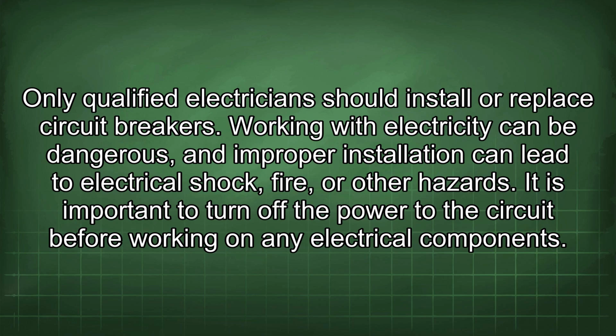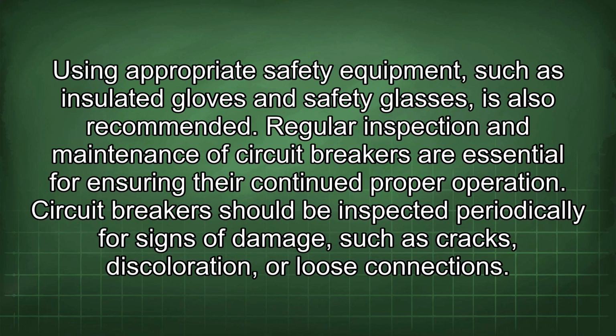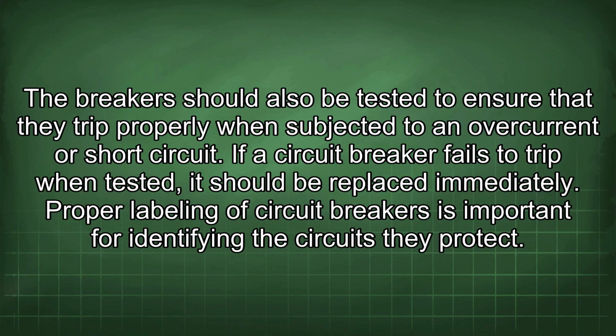It is important to turn off the power to the circuit before working on any electrical components. Using appropriate safety equipment, such as insulated gloves and safety glasses, is also recommended. Regular inspection and maintenance of circuit breakers are essential for ensuring their continued proper operation. Circuit breakers should be inspected periodically for signs of damage, such as cracks, discoloration, or loose connections. The breakers should also be tested to ensure that they trip properly when subjected to an overcurrent or short circuit. If a circuit breaker fails to trip when tested, it should be replaced immediately.